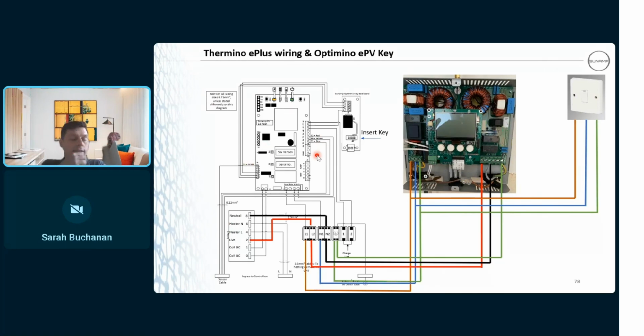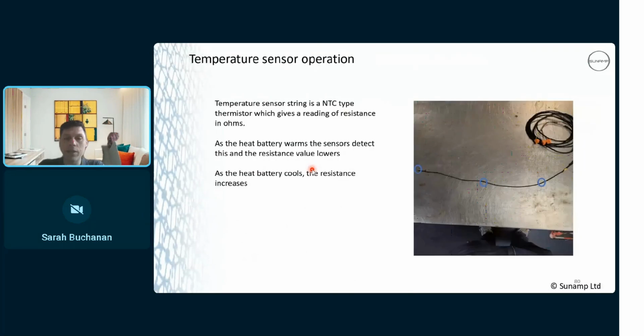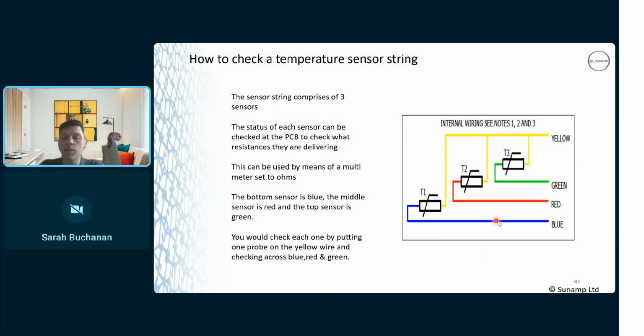If you don't have a current clamp to check the amps that you're pulling, this is all part of your commissioning. What you could do is take a resistance reading from yellow to blue, yellow to red, yellow to green, before you power up, and do whatever you need to do, tidy up your paperwork, and just before you put the lid back on, turn the power off again and take another resistance reading across your sensor. At least then you know the thing's charging up, and especially if it's your first one, you can hand that information over to the customer. Once you're up to temperature, you should be about 1.5 kilohms on the blue, 1.6, 1.7 on the red, and 1.7, 1.8 on the green.